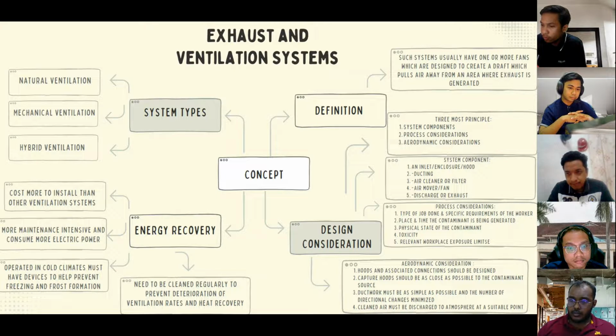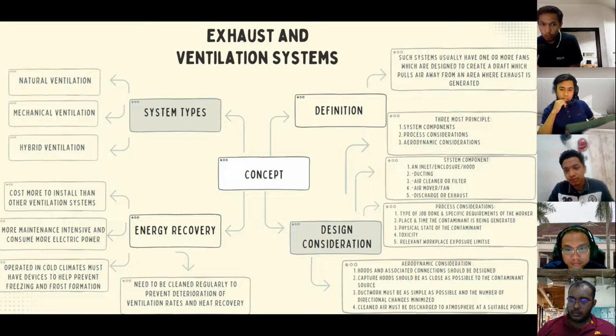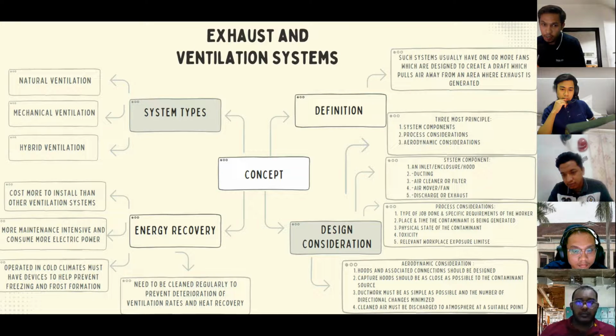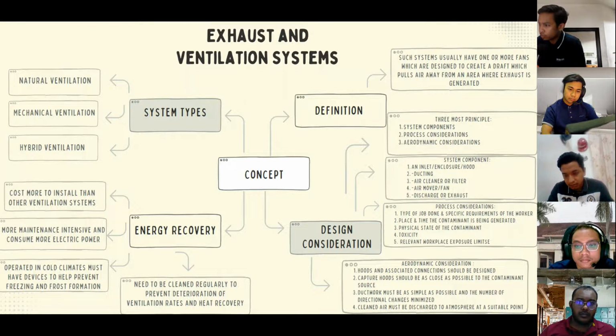For system components, there are five components. First, a hood or slot to capture the contaminant fluid at the point of generation. Second, ductwork to convey the contaminant away from the source. Third, a filter or air cleaning device to capture and remove contaminants from the extracted airstream. Fourth, a fan or air moving device to provide the necessary airflow. And the last is ductwork to discharge clean air to the external atmosphere at a suitable point.